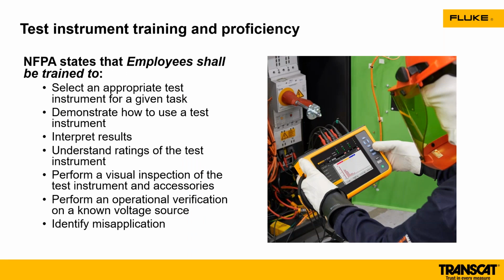So really, and I said this enough at the beginning, your employees shall be trained. Make sure that the employee is trained to work in that environment, that they select the appropriate test instruments, the gear that they need to use. They know how, they can demonstrate how to use these types of instruments. They can interpret the results. That's another key win on this. And understanding the ratings of those test equipment. You've got to know the category environment that you're working in to be able to know which equipment you need to work with, that you're going to do your visual inspections on the equipment and your accessories. You're going to perform those operational verification tests like that live-dead-live test. And even being trained, you can identify if there's a misapplication of equipment or something going on. So make sure that your employees are trained and know what they're doing.